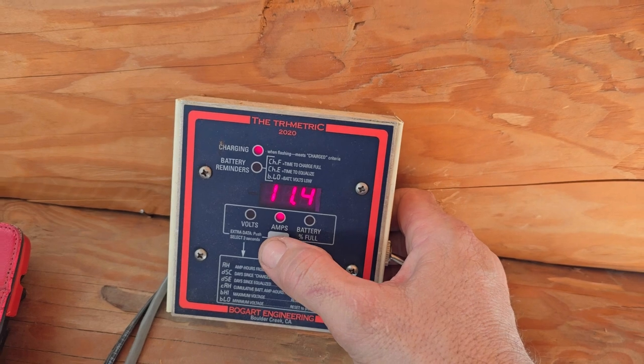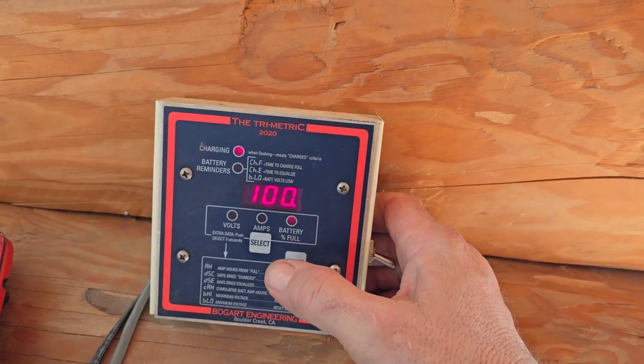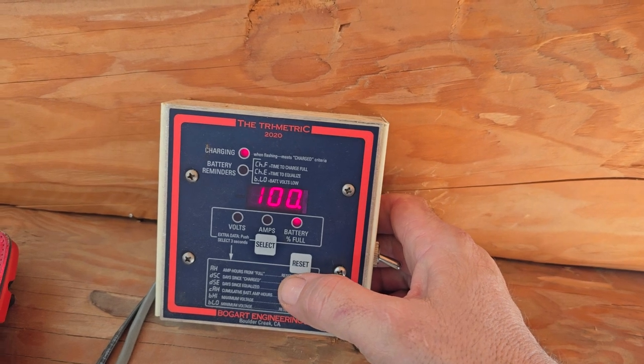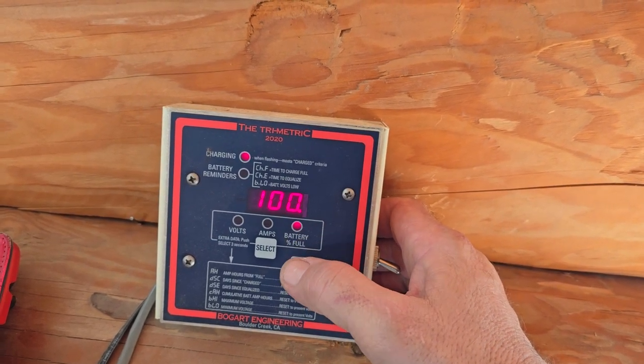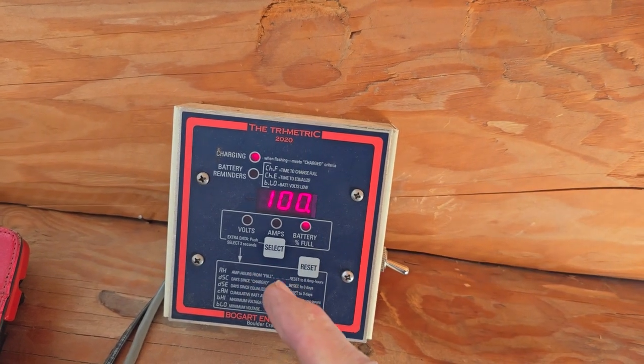It's showing 27.2 volts right now with 11 amps charging and 100%. Yesterday, the inverter shut off and the volts were down to 20 volts and at 86% battery capacity. That's a problem.